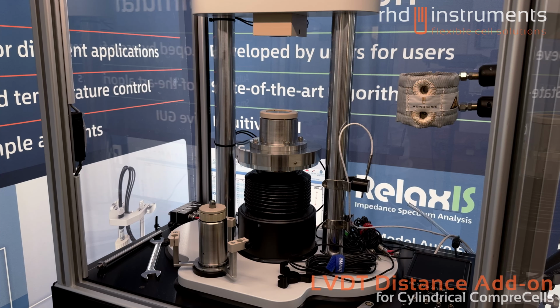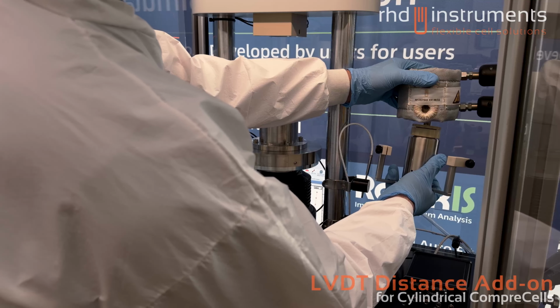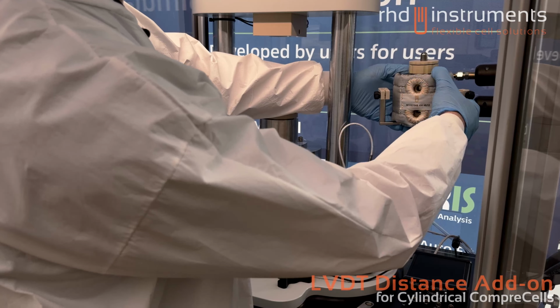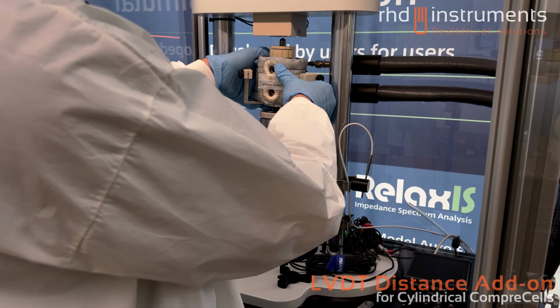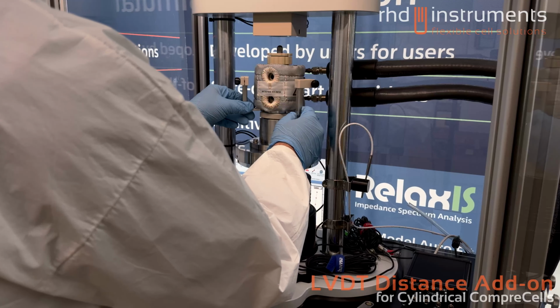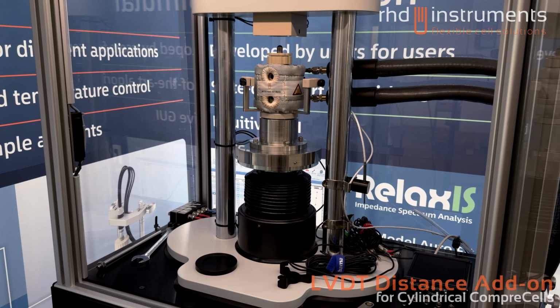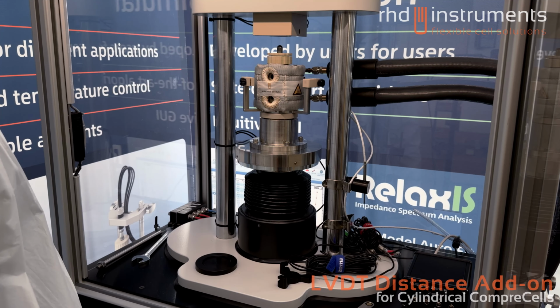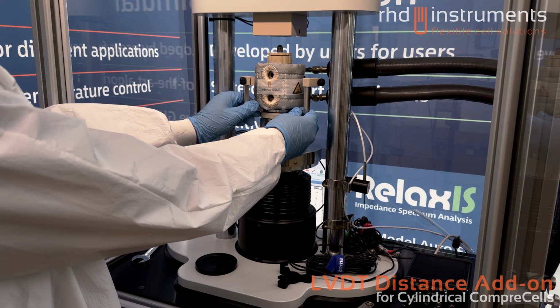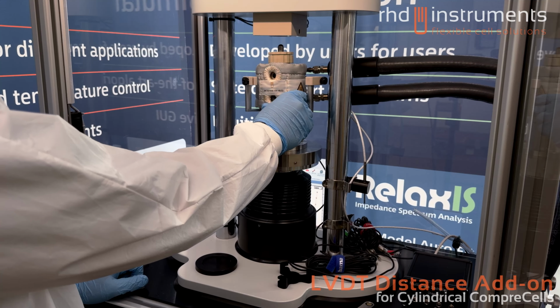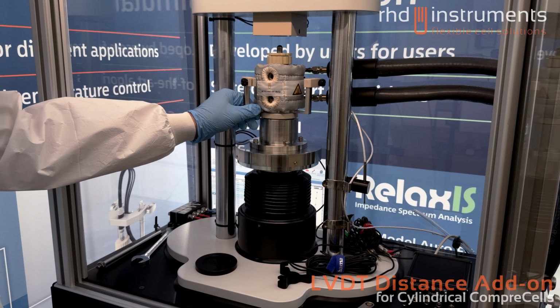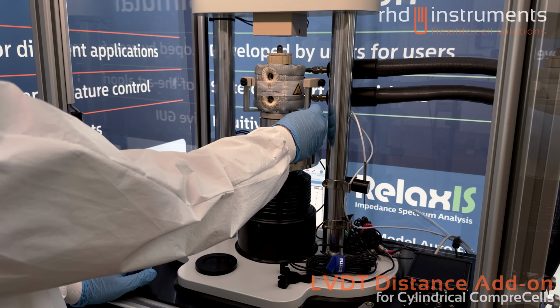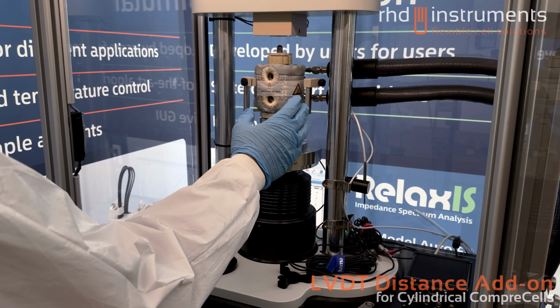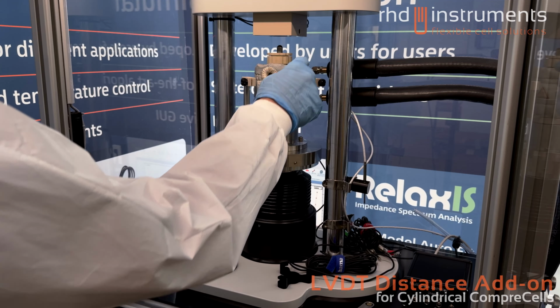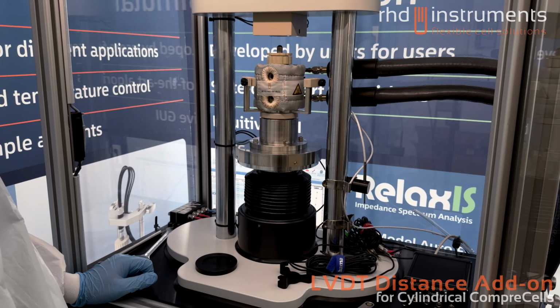If you want to have reliable dilatometry measurements, you need to have temperature control. So I'll go ahead and insert the cell into the thermal jacket. At this point, please make sure that the cell is well aligned and it sits steady on the platform. For example, if it tends to slip out of the peak ring in the bottom, like this, you have to realign it before you can approach the CompreDrive. Also, you can wiggle on the cell a little bit like this to make sure that it is well aligned. And if you have a permanent problem with tipping of the cell, most likely you need to rearrange the heating jacket by loosening the fasteners in the back here and realigning the heating jacket.